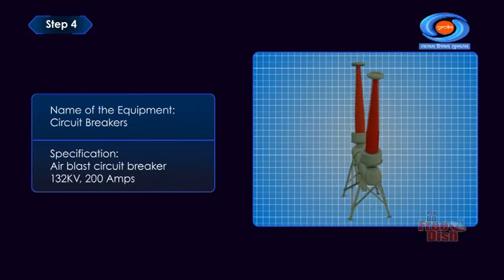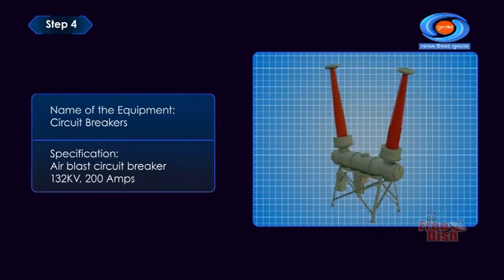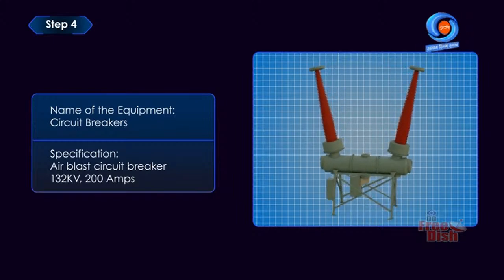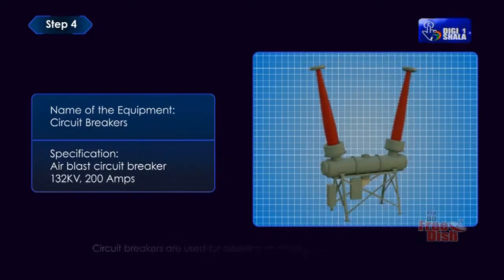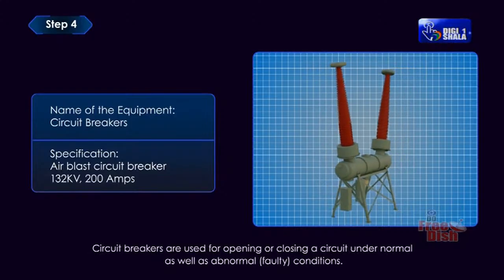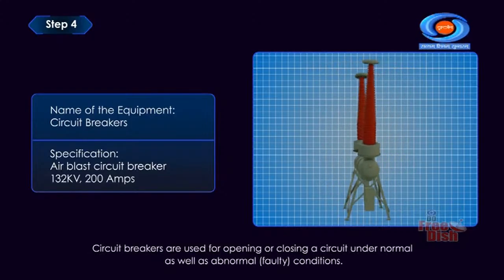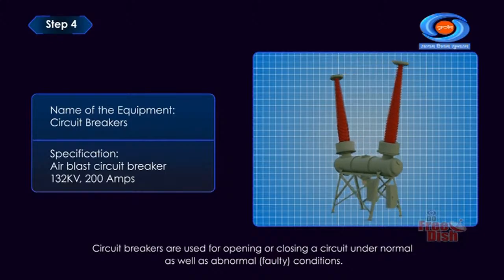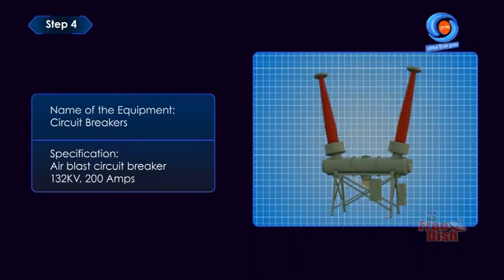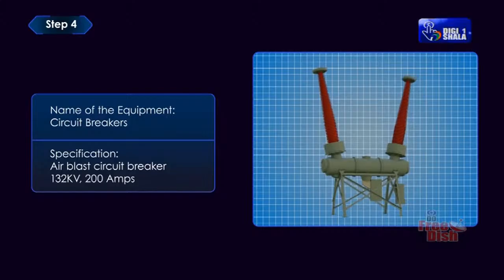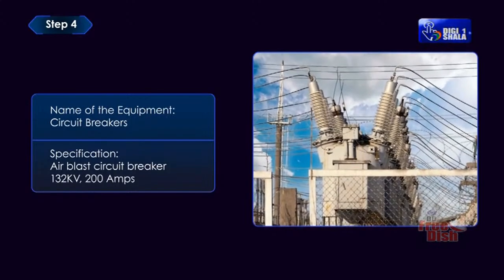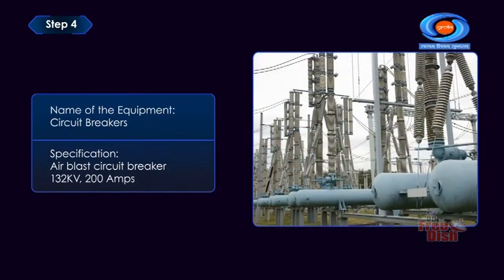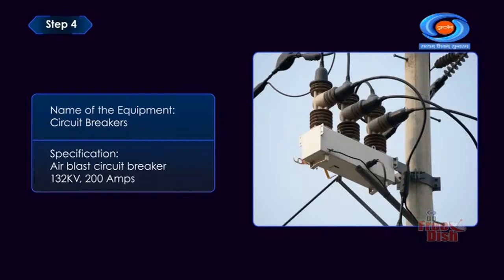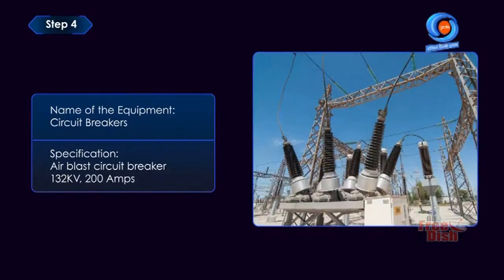Circuit breakers: air blast circuit breaker, 132 kilovolt, 200 amperes. Circuit breakers are used for opening or closing a circuit under normal as well as abnormal conditions. The different types of CBs which are generally used are oil circuit breaker, air blast circuit breaker, vacuum circuit breaker and SF6 circuit breaker.